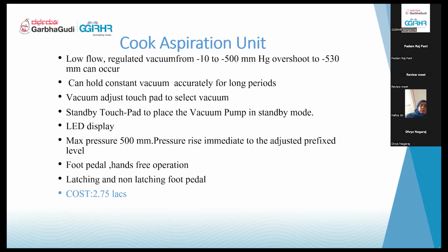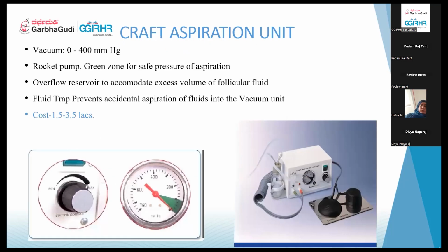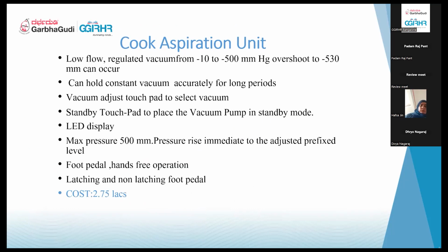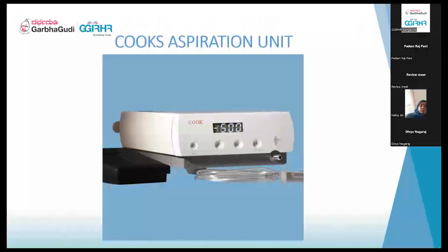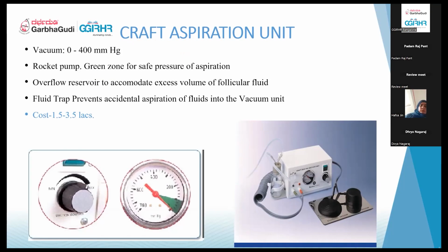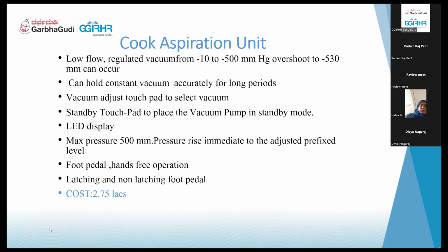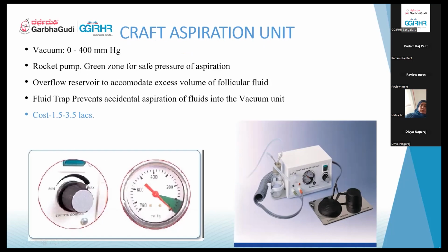It has a foot pedal, which will be controlled by the surgeon. This is another craft aspiration unit. This is cheap. This is a Cook aspiration unit. These are different brands. So for aspiration units, you have Cook's one, then there are craft ones. The only difference is cost: Cook's is 2.75 lakhs. This costs about 1.5 lakhs, and can go up to 3 lakhs also. This can create a pressure of up to 400 millimeters of mercury.